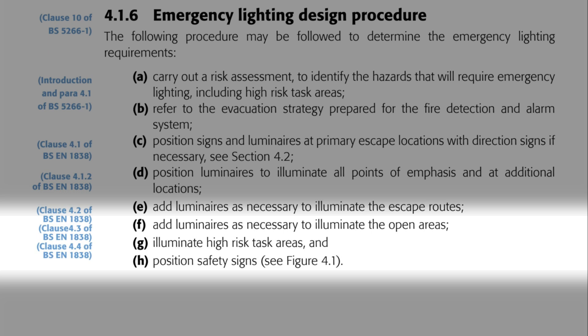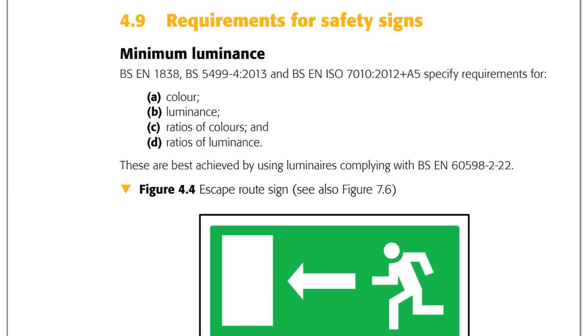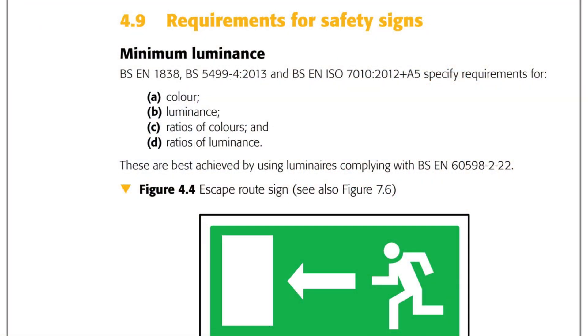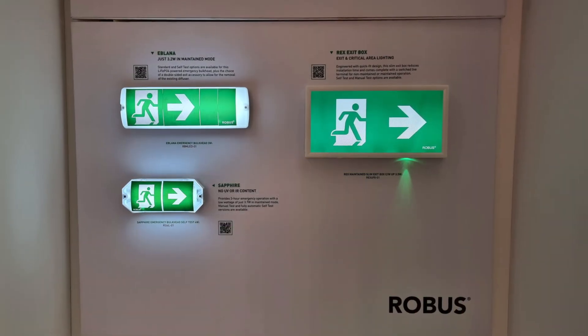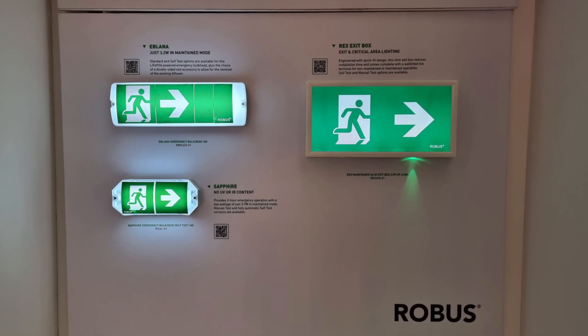This brings us back to signage, showing just how important this subject is. Subheading 4.9 gives requirements for safety signs including colour, luminance, ratios of colours and ratios of luminance. Some of these are outside the typical electrician's skill set — how many of us are familiar with RAL codes and colour theory? However, we find the reassurance that if we install emergency light fittings complying with BS EN 60598-2-22, like these ones from Robus, then we should meet those requirements.